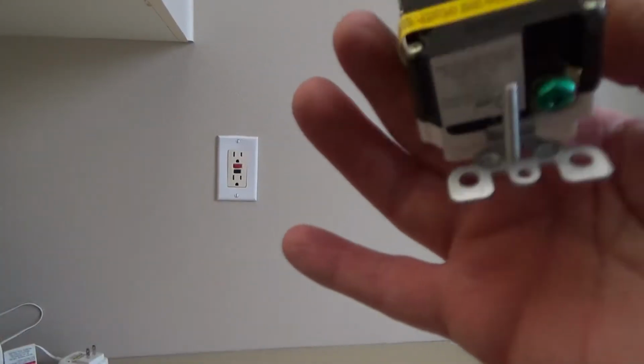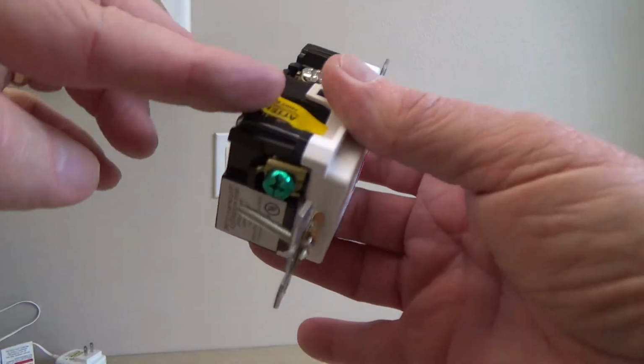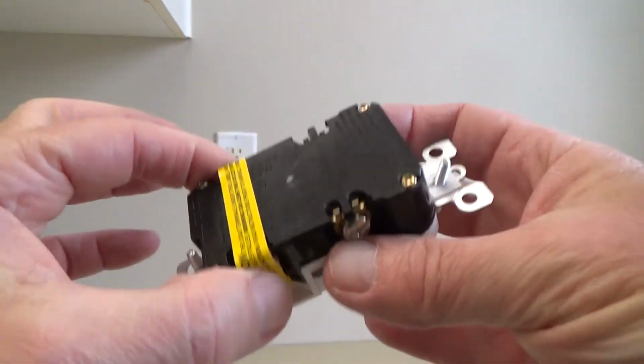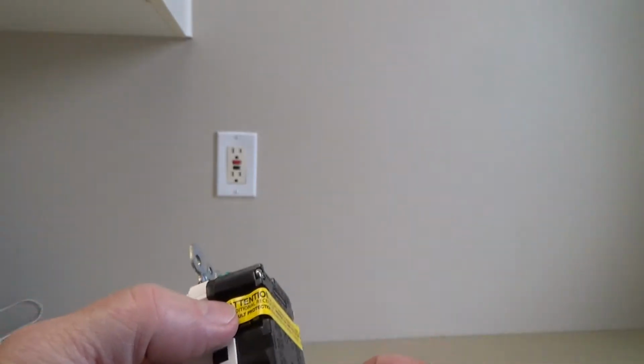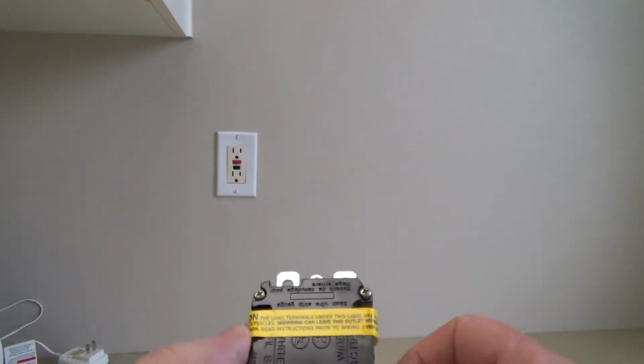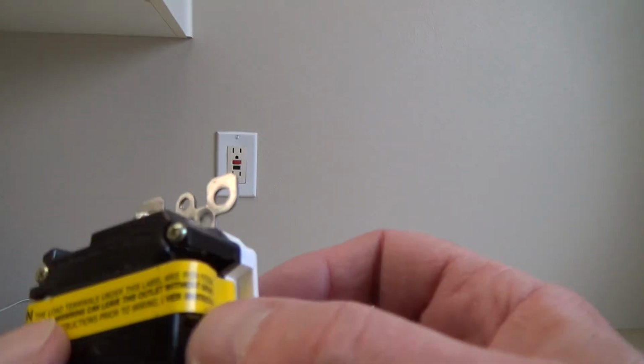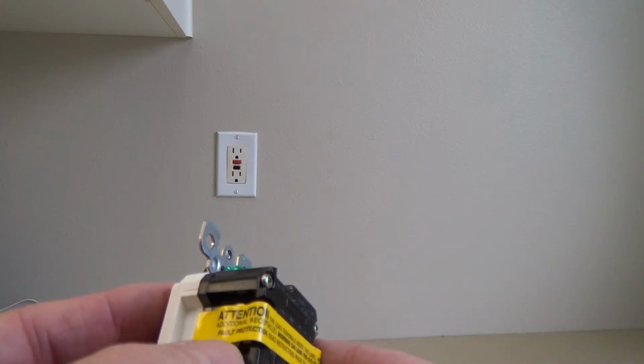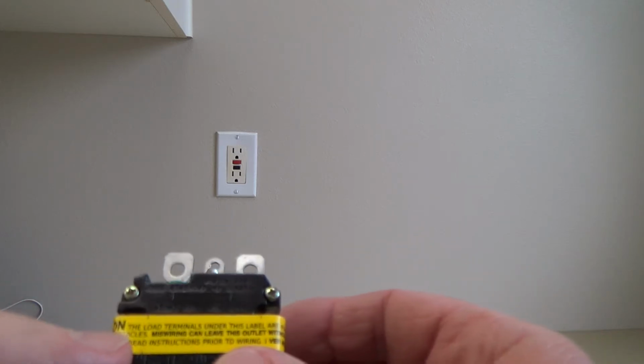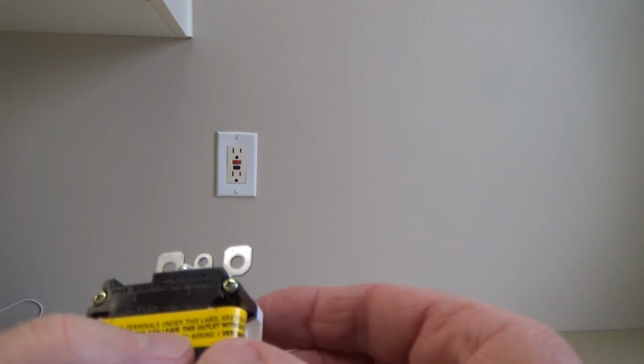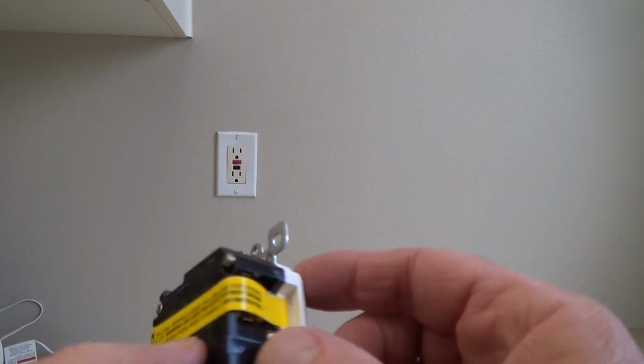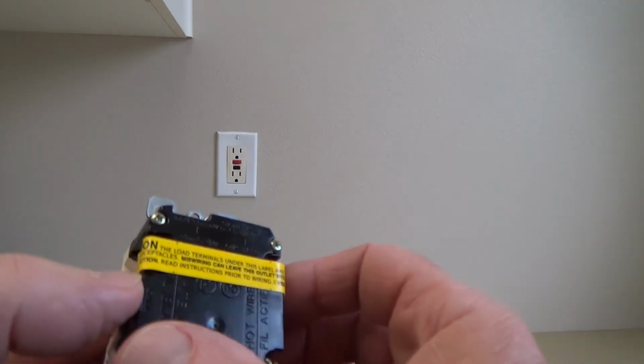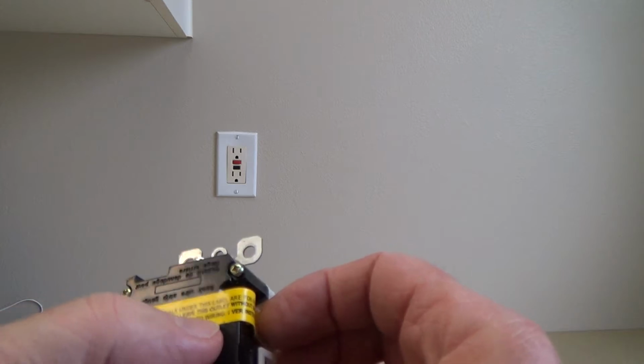To do that, you look on a GFI and see there's a yellow label. This is how they come out right out of the box. It says: attention, the load terminals under this label are for feeding additional receptacles. Miswiring can leave this outlet without ground fault protection. Read instructions prior to wiring.